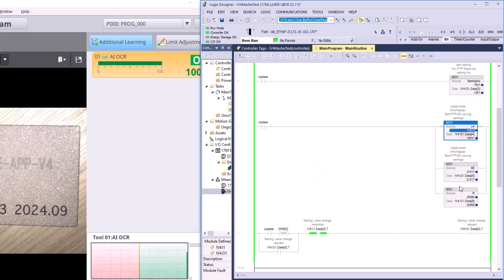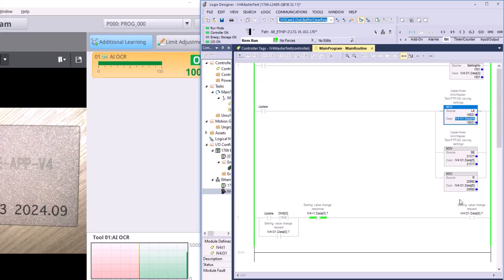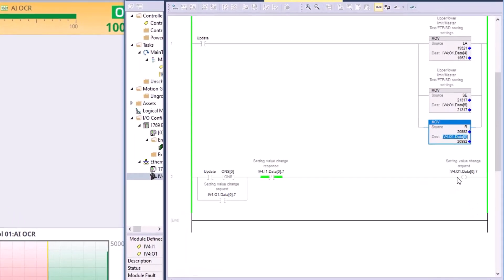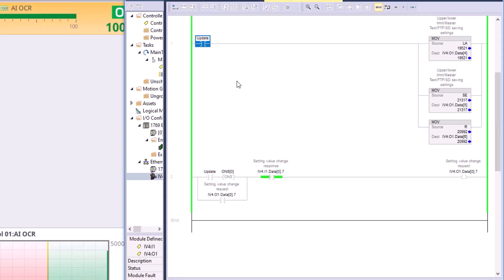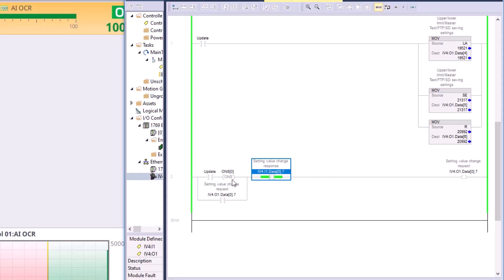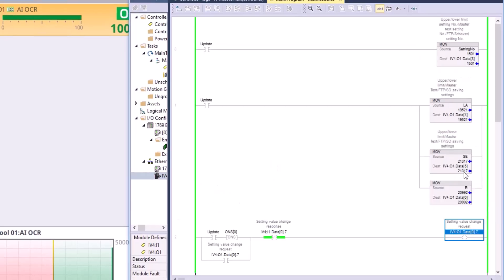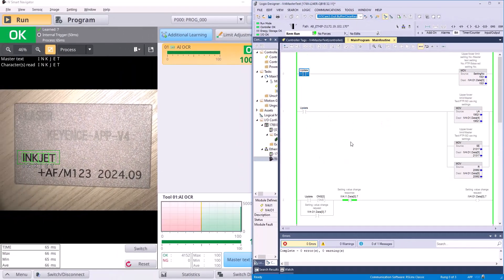Then, with these words written, we're writing the letters into our outputs. So now we've told it what kind of update we're doing, we've told it what we want to update the text to, then all we have to do is execute a setting value change request. The master text is sort of a setting value and we're changing the value of that text. So, when we activate this update bit, it's going to send this through. This is the standard request, response, self-latching circuit we recommend for triggering, program changing, etc. This is how you normally do it. If this is a trigger request, it would be trigger request and trigger response here, normally closed type bit. So, with that all said, now we can see how this works here.